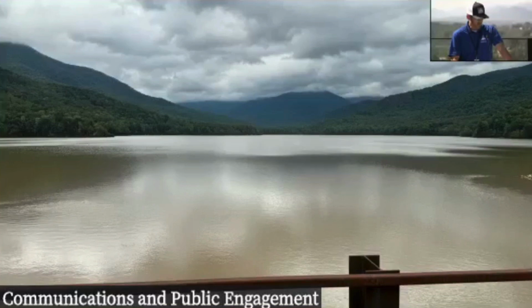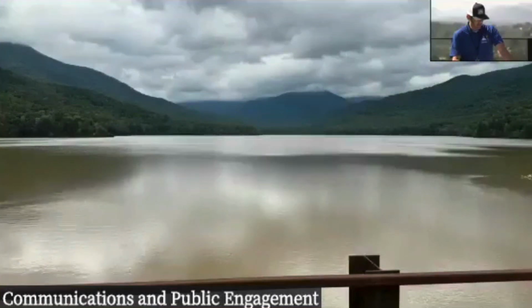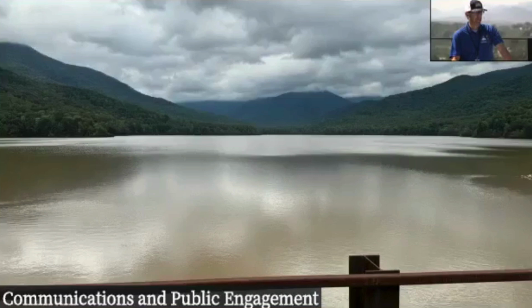So that's something that we're monitoring. But what happens is every day that passes, the turbidity in that water begins to settle. That's a natural process. And that's occurring as we are making these repairs to the distribution system. One of the things that is important to note is we are able to intake water at different depths. So there are different points in the water column that we can get water into the treatment system when it's ready. We're able to change that. So we're monitoring the water column to make sure we know where the water is that has the least amount of turbidity, and that's where we'll be able to get the water from when that time comes.